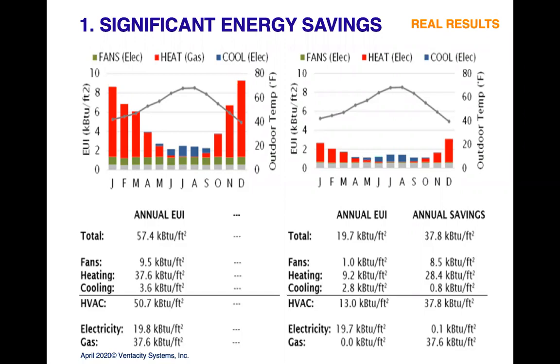certified HRVs. And the result, as you can see, we went from the building EUI of 57 down to about under 20. And the HVAC went from 50 and change down to 13 kBTUs per square foot. So it's an over 70% reduction in energy.